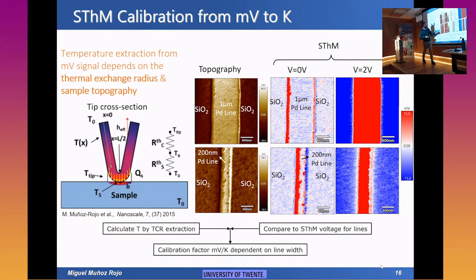Based on that, we can produce SThM images. We already see some features, some artifacts caused by these topographic changes between the substrate and the line. But we can also clearly see, when we apply power to the line, how it heats up uniformly. So we know the temperature of the line thanks to the TCR, the temperature coefficient of resistance, and we know the SThM voltage from our measurement, from our technique.